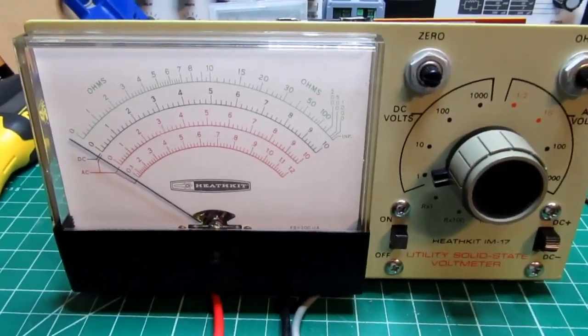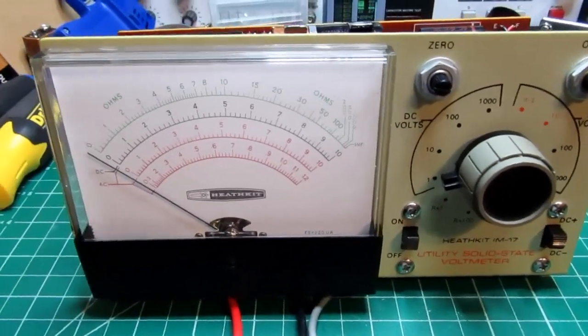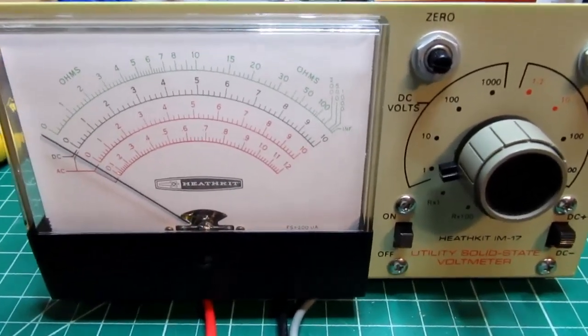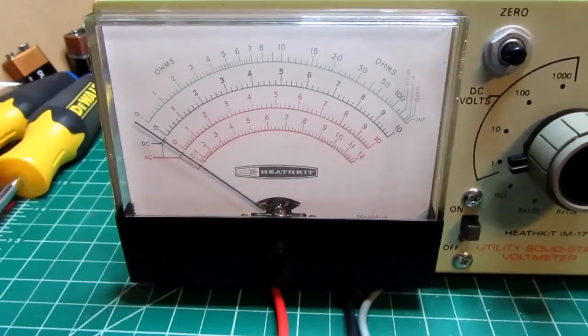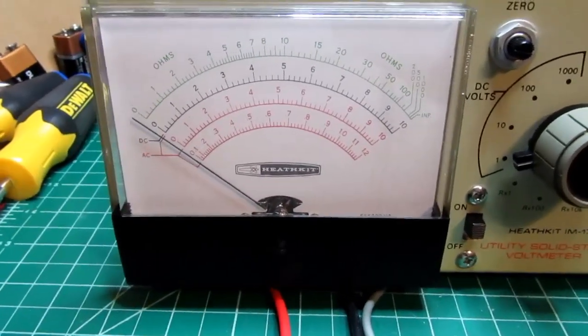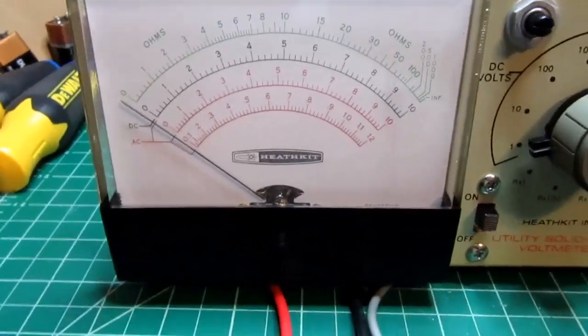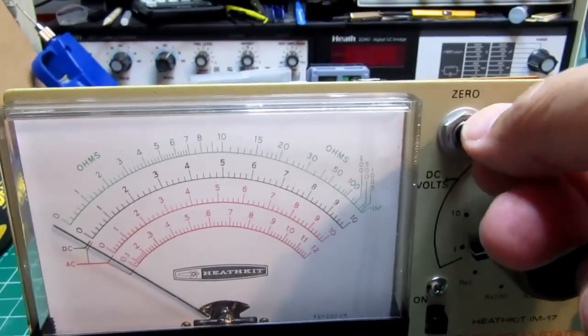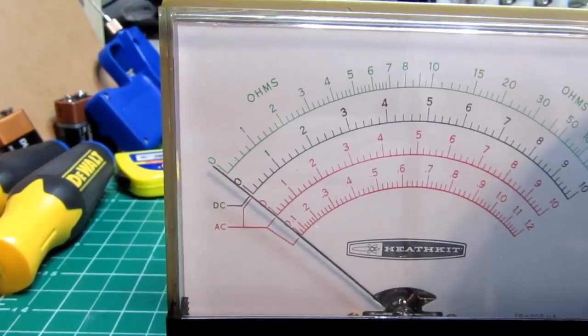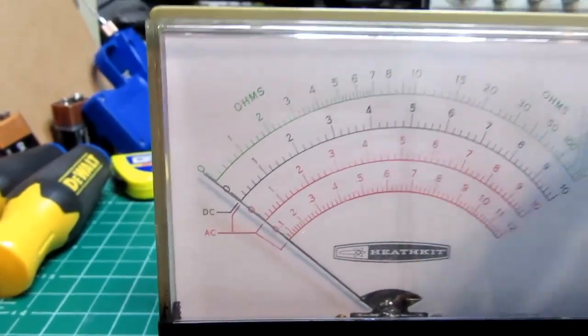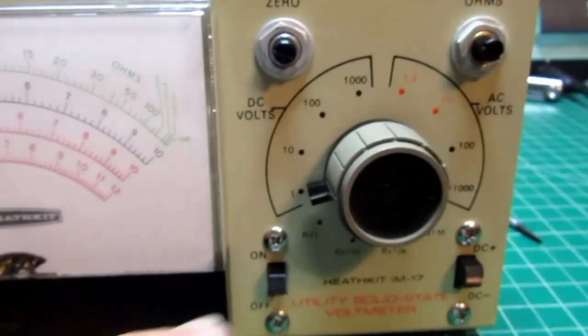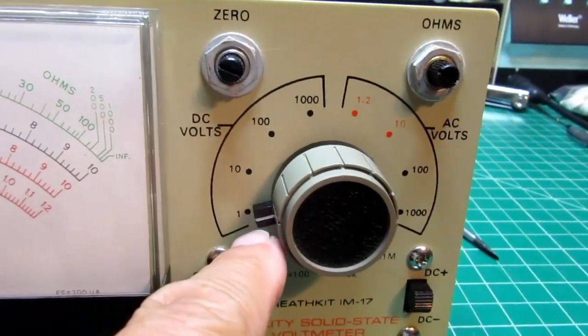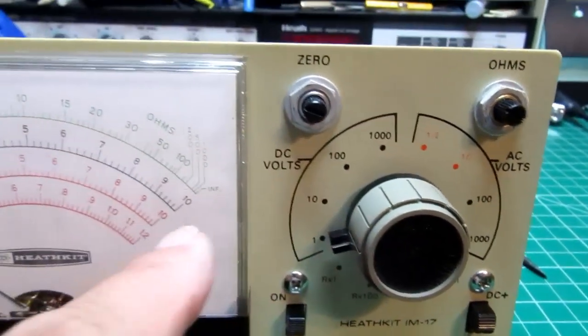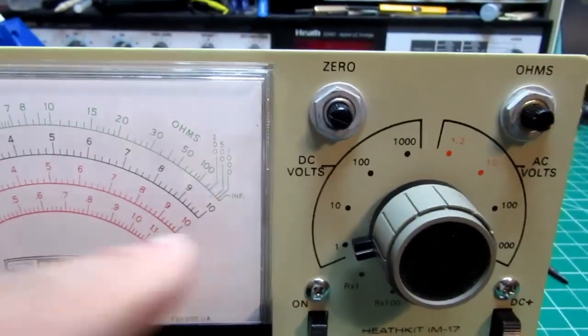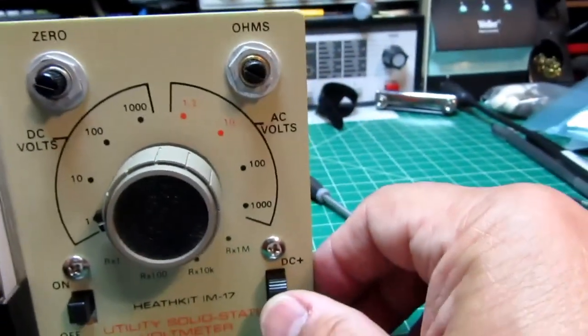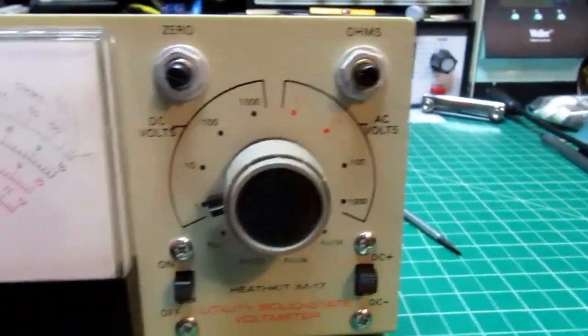Okay, let's do a demo. I've just completed the calibration process per the Heathkit manual. And first off, I need to zero out the meter, so I take the zero control here and adjust it until it's right on 0. And I'm in the DC volts lowest range, so 1 volt would be full scale, 1 volt would be up here, and I've got the DC plus and minus switch in the plus position.